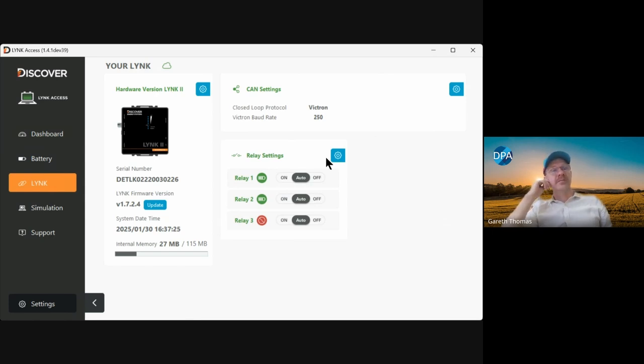Even if the pass-through is not working on the input side of the inverter, there'll be power. So that's pretty useful. In Victron, because the Cerbo is powered on the DC side, it's not as much of an issue, because even if you lose the inverter, it would still start the generator. But with other inverters, I think this is a good alternative to their inbuilt generator, and you can do quite a bit more with it as well.